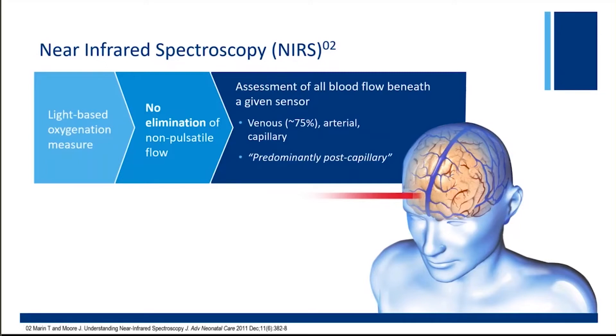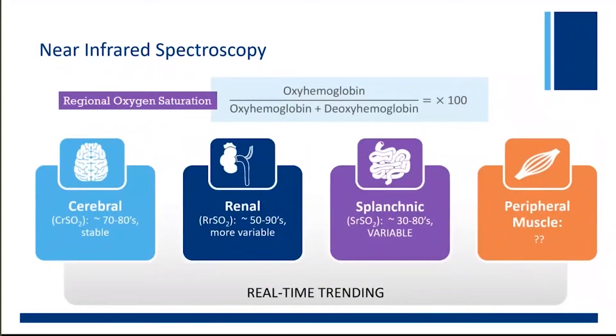That allows for regionalization. Since we're looking mostly at a venous oxygenation, the arterial signal is minimized. That means you're looking at how much oxygen is left in that segment of tissue after that tissue has already extracted its metabolic oxygen needs — a predominantly post-capillary measure. The oxyhemoglobin divided by total hemoglobin equation is exactly the same as used in pulse oximetry, but the number here is venous; therefore, it's expected to be lower. Cerebral oxygenation runs in the 70s to 80 percent range and is generally stable.